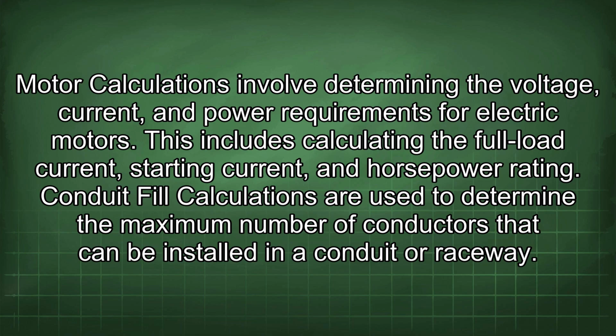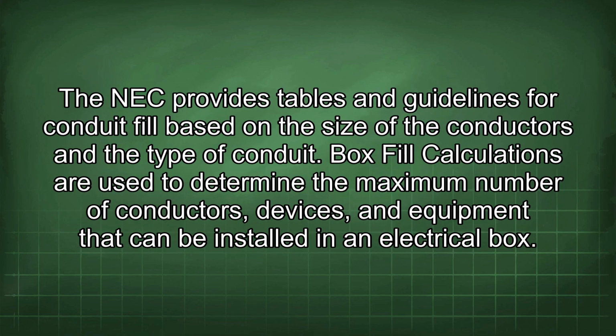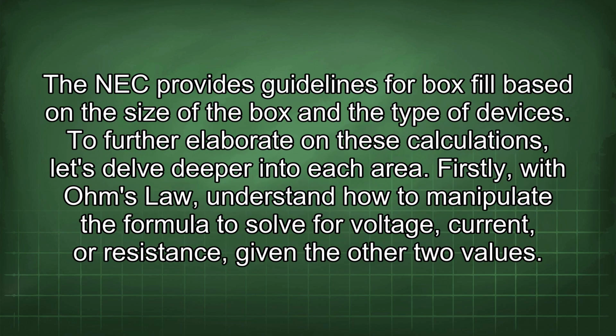Conduit fill calculations are used to determine the maximum number of conductors that can be installed in a conduit or raceway. The NEC provides tables and guidelines for conduit fill based on the size of the conductors and the type of conduit. Box fill calculations are used to determine the maximum number of conductors, devices, and equipment that can be installed in an electrical box. The NEC provides guidelines for box fill based on the size of the box and the type of devices.